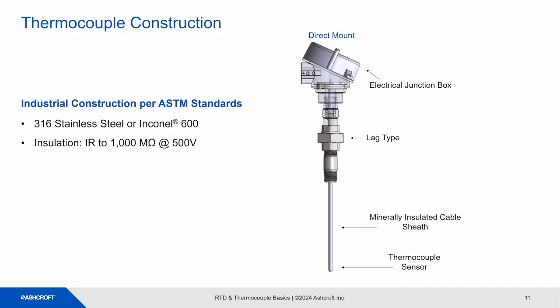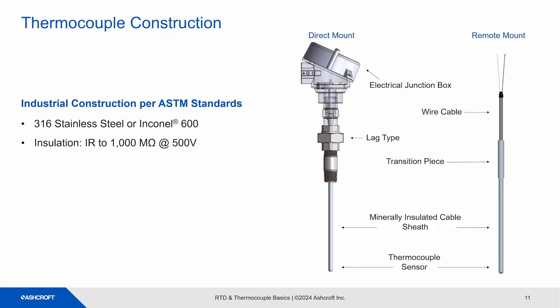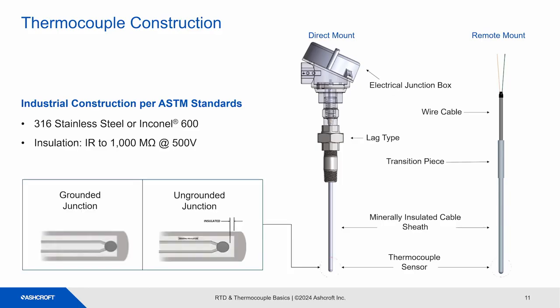There are also remote mount probe styles. The thermocouple sensor is at the tip of the probe. They use MI cables. They have a transition piece to connect the MI cables to the extension wire cable. The wire cable can come in a variety of wire insulation types, and they can have flex armor for additional protection. There are two types of junctions, grounded and ungrounded. Grounded junctions have the junction welded to the probe tip. Ungrounded is the most common, with the junction isolated from the probe tip.